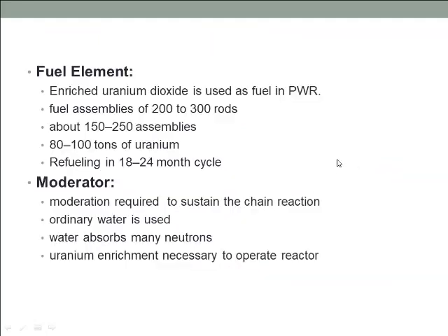Let's start with the fuel element. Like the boiling water reactor, enriched uranium dioxide is used as fuel in the pressurized water reactor. Fuel rods are grouped in fuel assemblies called fuel bundles that are used to build the core of the reactor. A typical pressurized water reactor has fuel assemblies of 200 to 300 rods each, and a large reactor would have about 150 to 250 such assemblies with 80 to 100 tons of uranium in all. Usually, refueling in a pressurized water reactor is performed after an 18 to 24 month cycle.